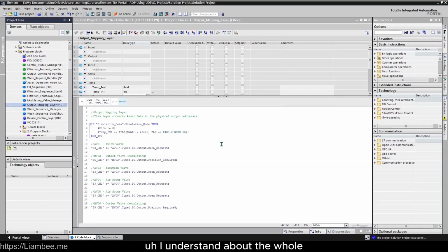I understand about the whole interface updating and things like that, that you can reserve memory, but with a properly laid out program and some management around your data, reinitializing data and restoring from a snapshot, in most cases can be done on a live plant anyway. And the trade-off for optimized data is actually a slower CPU scan. So I'd rather have the speed and manage my data accordingly.